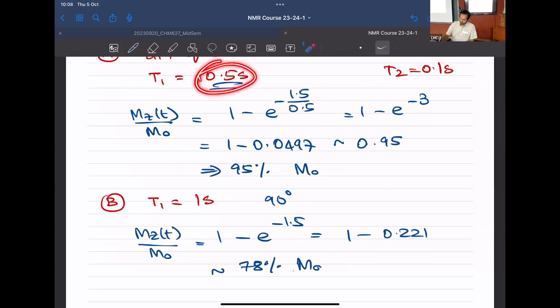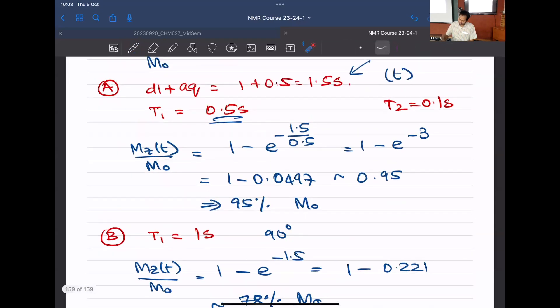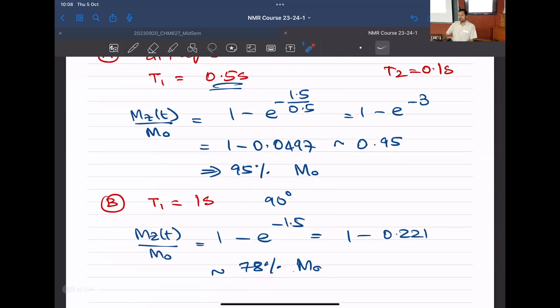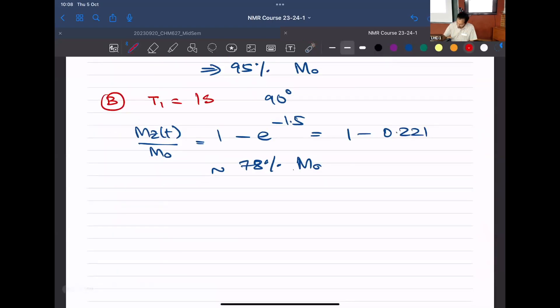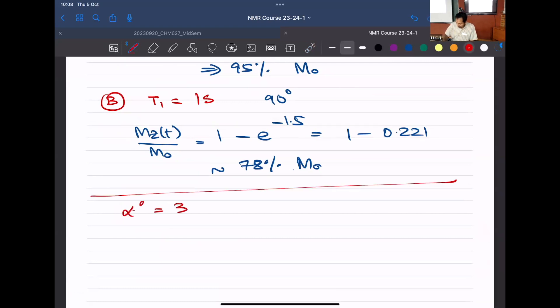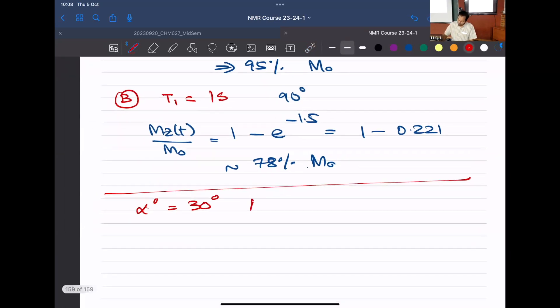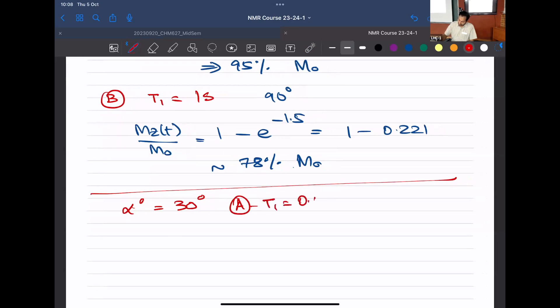It's not surprising that if T1 increases, the recovery within a fixed D1 + AQ is smaller. Systems with longer T1 require longer D1 + AQ. For large systems, AQ is not appreciable; D1 is the major factor, which is why people refer to D1 as the recycle delay. Now let's do the same exercise for a 30-degree flip angle instead of 90 degrees, for both T1 = 0.5 s (case a) and T1 = 1 s (case b).